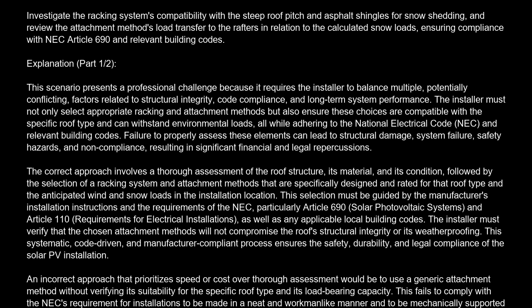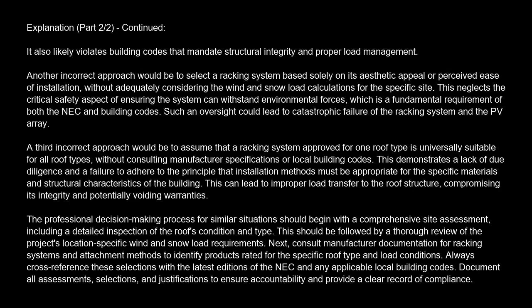An incorrect approach that prioritizes speed or cost over thorough assessment would be to use a generic attachment method without verifying its suitability for the specific roof type and its load-bearing capacity. This fails to comply with the NEC's requirement for installations to be made in a neat and workmanlike manner, and to be mechanically supported and protected from damage. It also likely violates building codes that mandate structural integrity and proper load management.